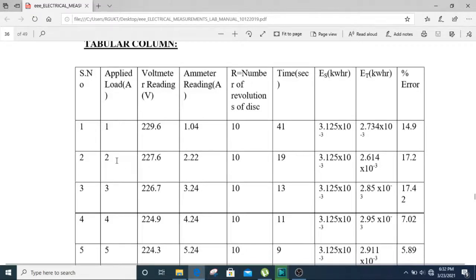Next you take a 2 amp load, note down the voltmeter reading, ammeter reading and time taken to complete 10 revolutions, and you find the true energy. True energy is voltmeter reading into ammeter reading and the time taken by the energy meter to complete 10 revolutions. Here it is 19 seconds. Similarly, you apply a 3 amp load, and voltmeter reading into ammeter reading and time taken to complete 10 revolutions will be the true energy.